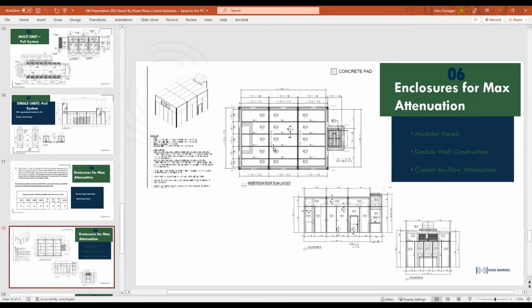Typically, we get into a double wall application here - you can see there's the inner wall, there's the outer wall. There's no way to get to some of these 'max attenuation' levels without getting into a double wall situation, and the muffler will be inside of our enclosure. We handle the thermal issues with that, because the heat load from standby power is intense, but it stops any bit of radiating out of the pipe and really lets the true performance of what will be a really stringent muffler system be just the exhaust of the muffler. You'll see that in the last picture. That's another case where we handle everything inside - you're not going to have a remote cooling situation here. There's more attention paid to the air, heat load, ventilation, and silencing of that than almost anything else.